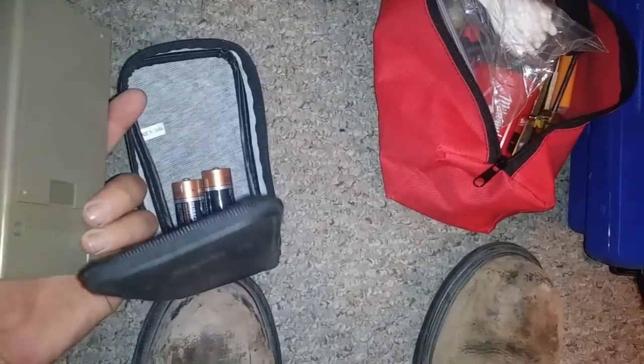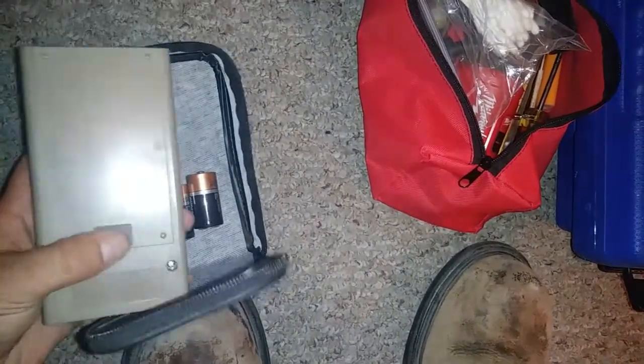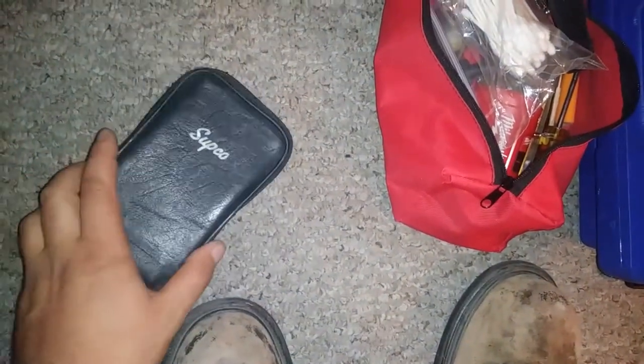This is an older version — I bought the new version but that was one of the things that got stolen. This is the Supco M500 megohmmeter, kind of a classic. It's not the most accurate but it'll definitely tell you if you've got bad windings, which is all you really need.